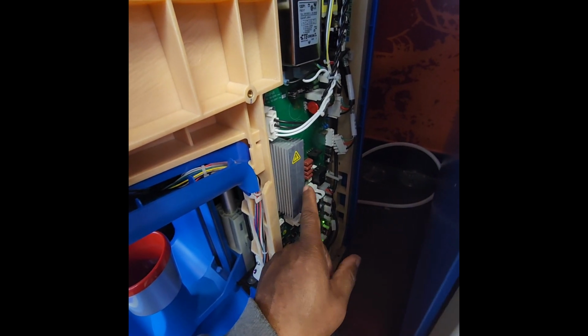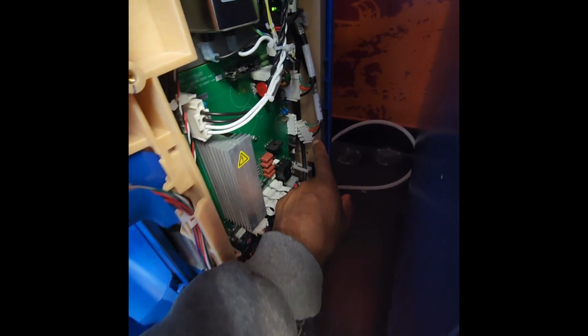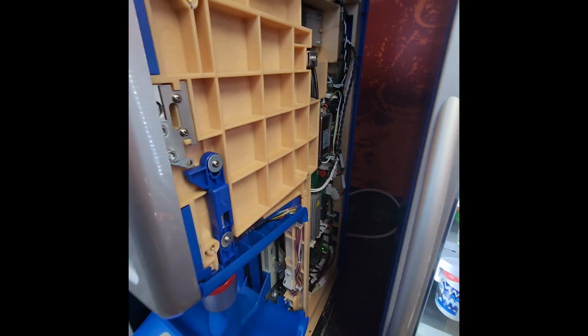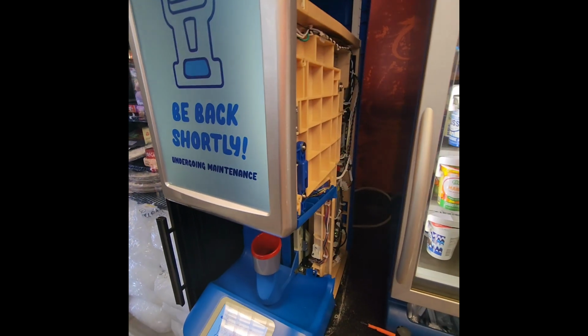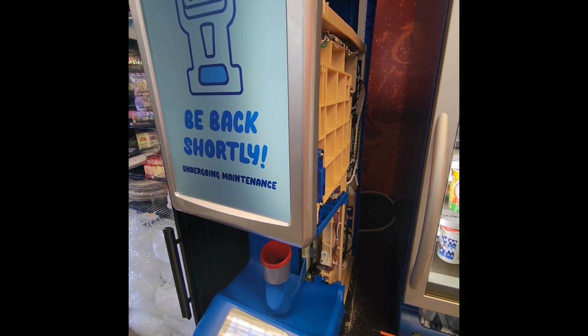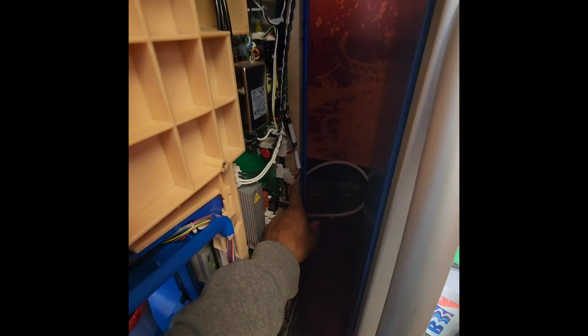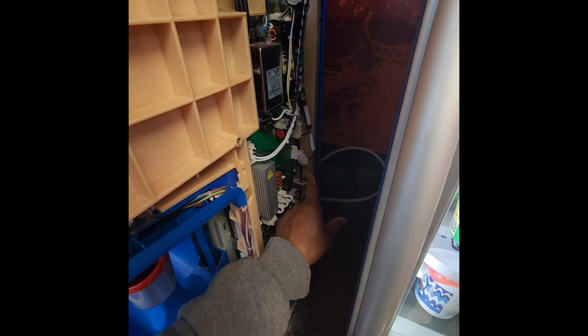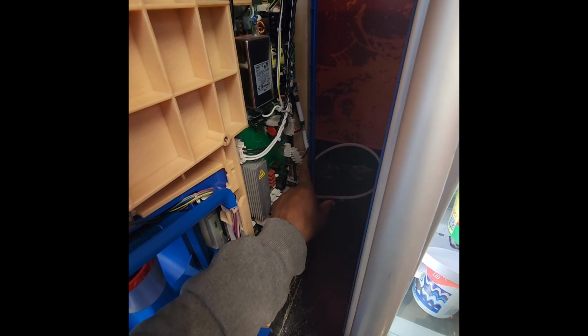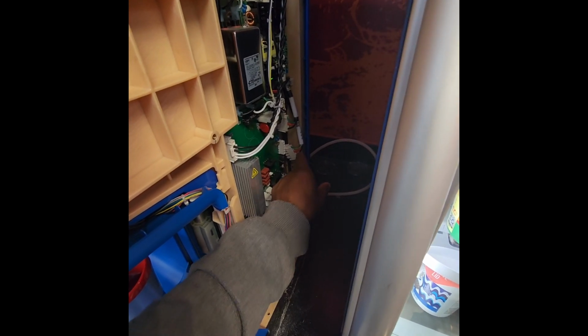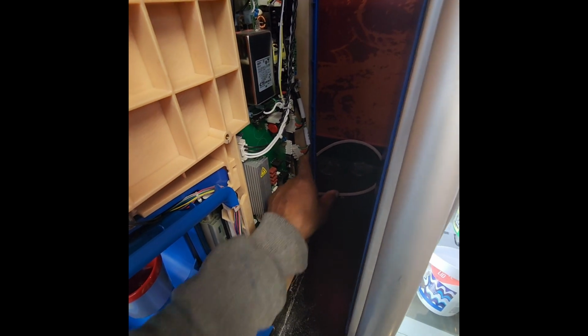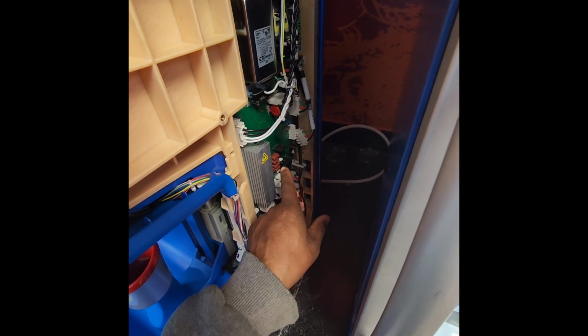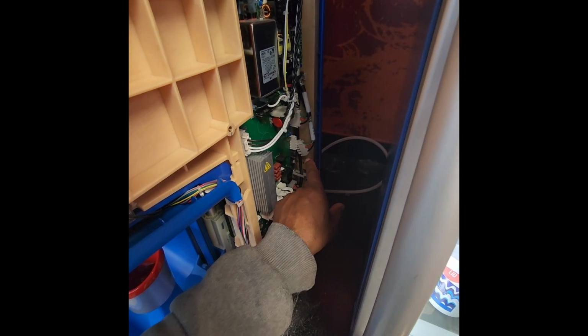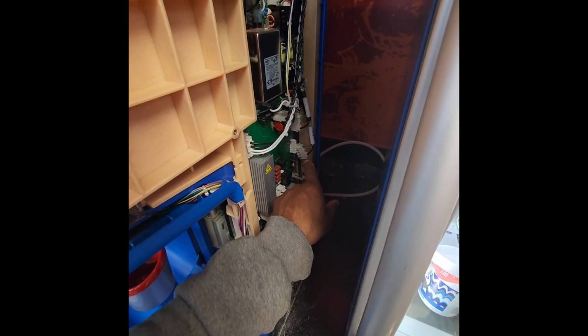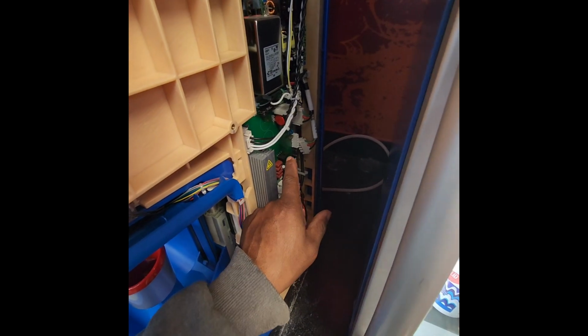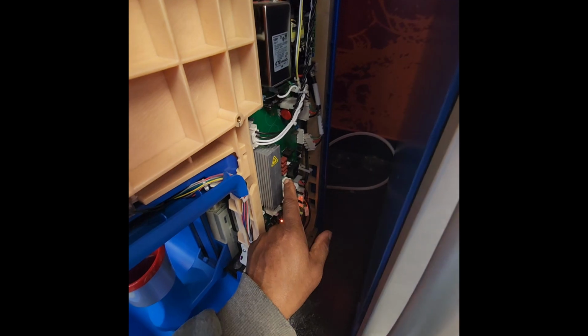So we will have to send out a board and a new pump motor, and replace those at the same time, because if you don't, you'll wind up going back and forth to the site. If I just change the motor, it's still not going to work, and that board could damage the new motor. If I try to change just the board, that new board can get damaged because of the motor. So it's best to change the motor and the board together.